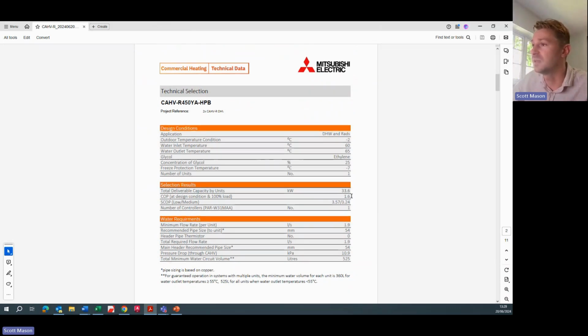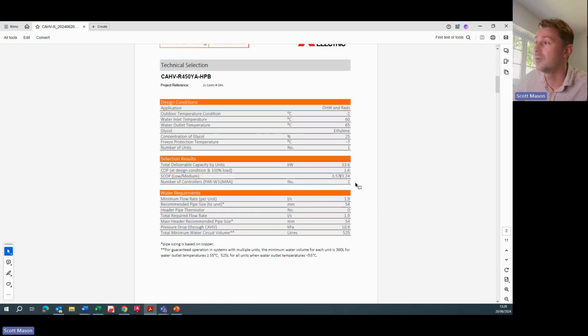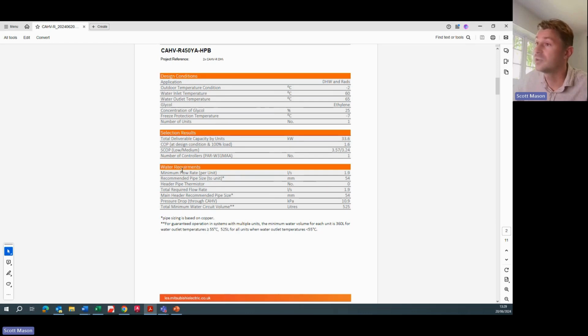It will give you site-specific information, like what's my efficiency at my design condition, how many kilowatts am I actually going to deliver at my design condition, how many controllers I need, etc., which we'll look at on the quotation tools shortly. And it also gives you things which are incredibly important to the unit's application. My unit is a 40 kilowatt heat pump generally. That means I need 1.9 litres a second, which translates to a 5-degree delta T. That means I'm flowing at 65 and returning at 60.